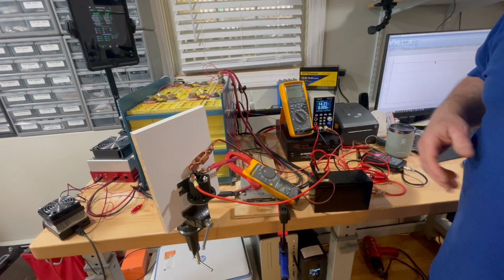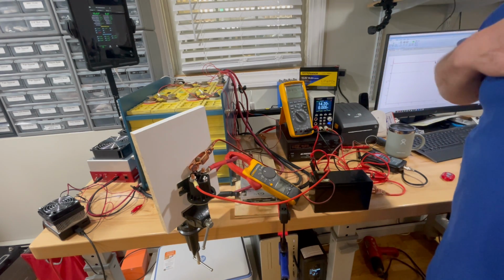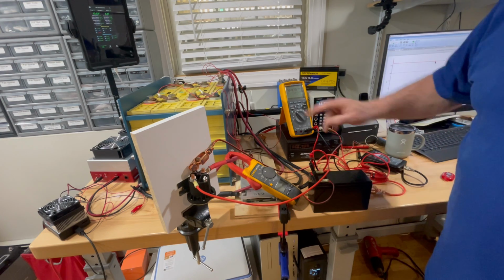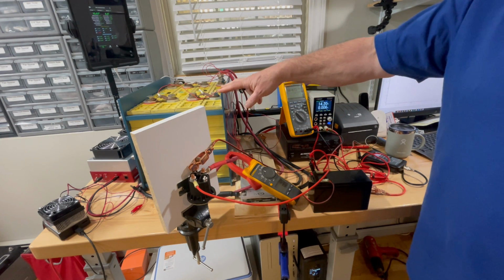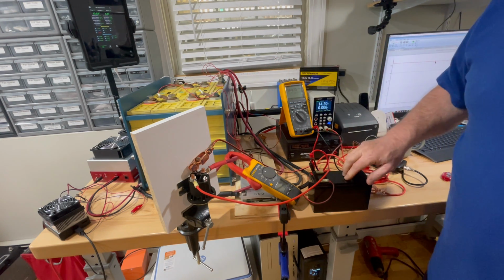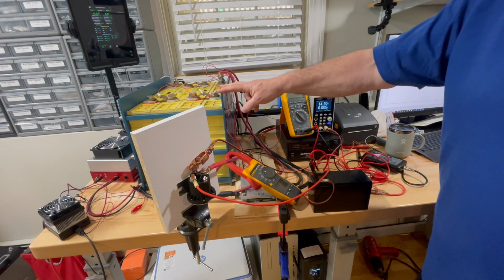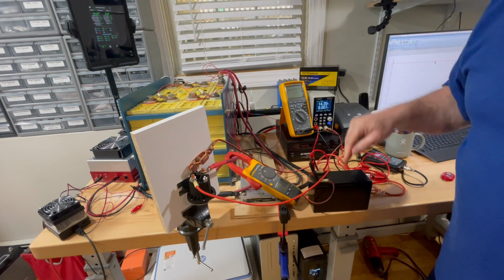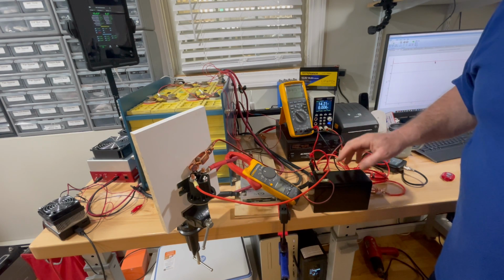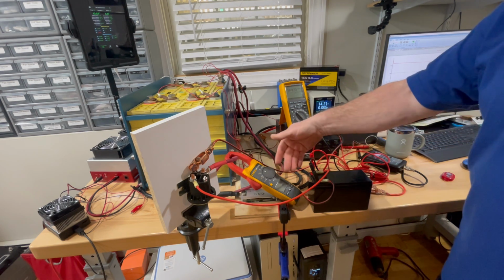So they don't just balance out. You need a charge voltage there to get them in balance. That's why the manufacturers tell you that, because in series, the batteries will never balance. But in parallel, they'll eventually balance, but you have to have a charge voltage in order to make that happen. So that's why they tell you to do this.